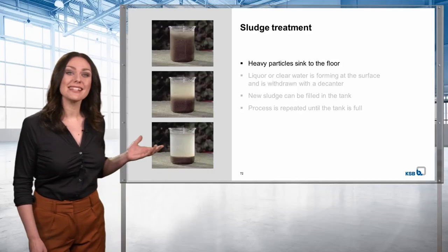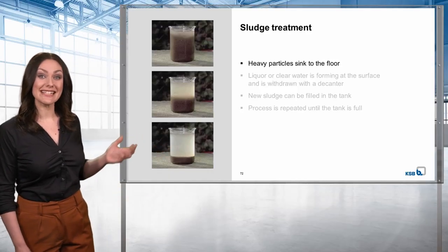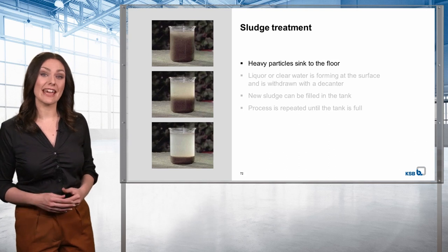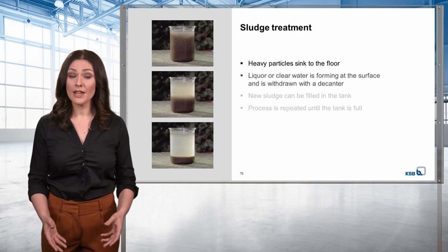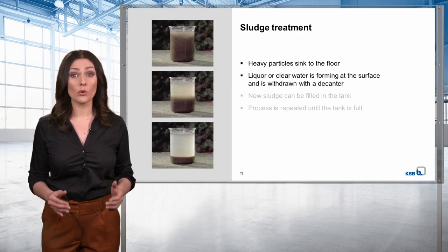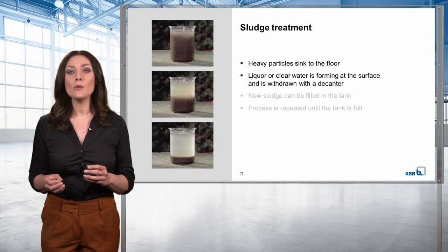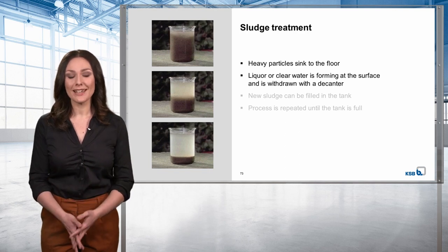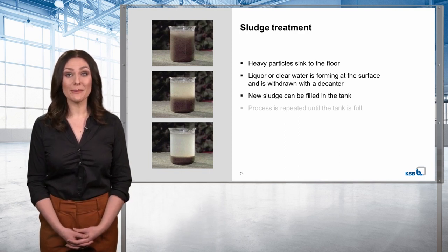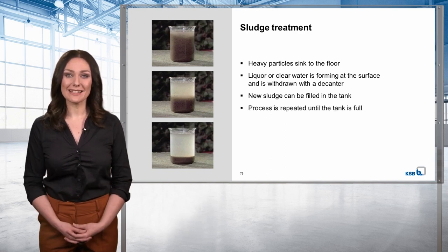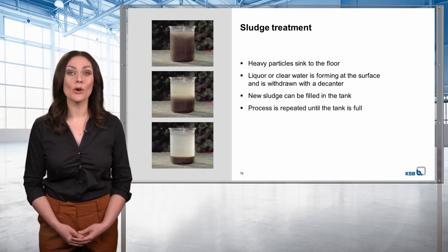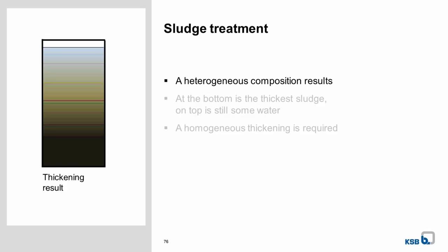Here you can see a classic thickening process in detail. In the sludge tank, the sludge remains untouched until the heavy particles have sunk to the floor. The so-called liquor or clear water forming at the surface is then withdrawn with a decanter. This creates more storage volume in the tank that can be filled with new sludge. The process is repeated until the tank is full and no more liquor can form.